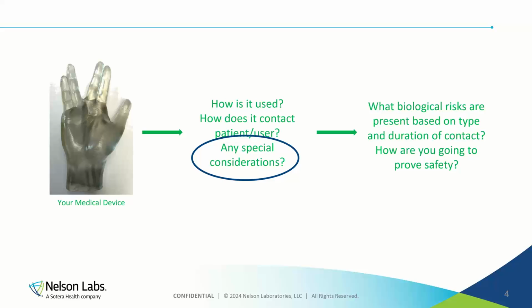You look at the table in ISO 10993-1, and then you just say, these are the endpoints to be tested, and you just test them. If the test comes out as clean or passing, then you're good. However, first of all, I do wonder sometimes, if we are just following that strategy, are we really capturing all of the risks that are associated with some device, right?